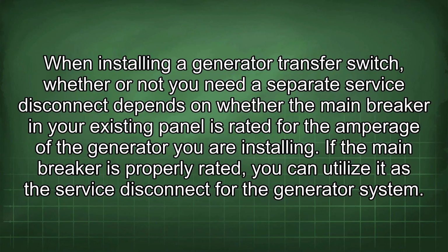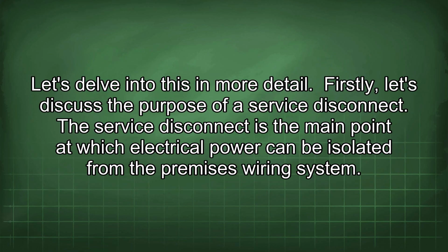When installing a generator transfer switch, whether or not you need a separate service disconnect depends on whether the main breaker in your existing panel is rated for the amperage of the generator you are installing. If the main breaker is properly rated, you can utilize it as the service disconnect for the generator system. Let's delve into this in more detail.